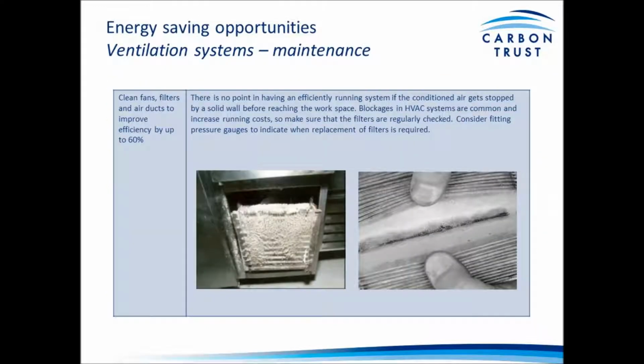Maintenance is again critical for ventilation systems. Typically, the easier you can make it for air to flow around the ventilation system, the less the fan has to work to provide effective ventilation. So it should be part of standard maintenance to check filters and intakes regularly. Pressure gauges on air handling units will indicate if the filter is heavily blocked, and you can often improve efficiency by up to 60% if the system is particularly clogged. Air intakes will often be external, sometimes in challenging positions, but it is worth reviewing.